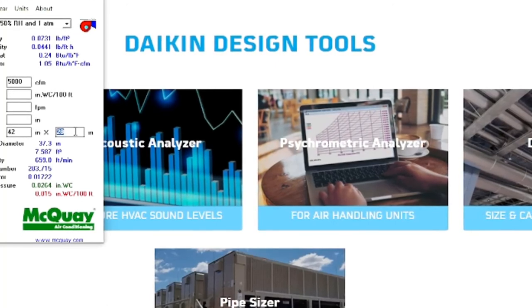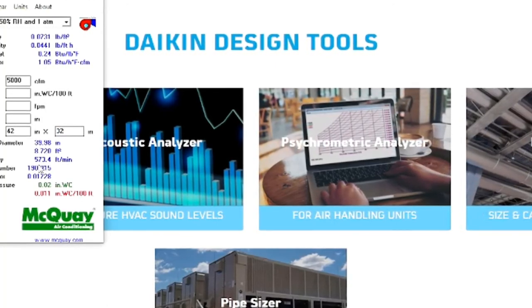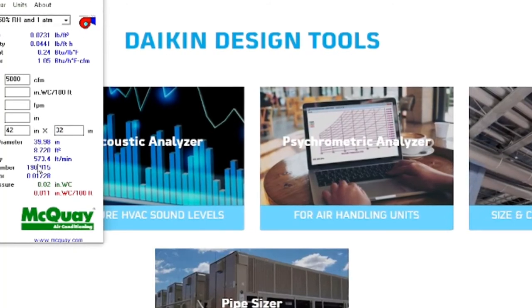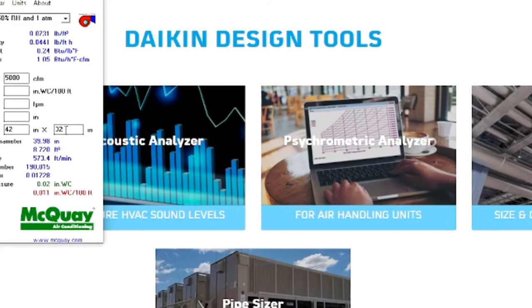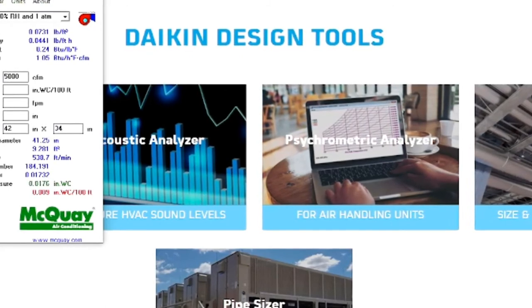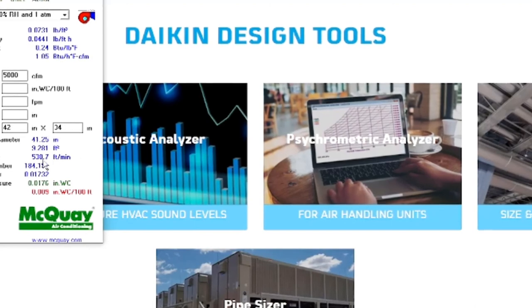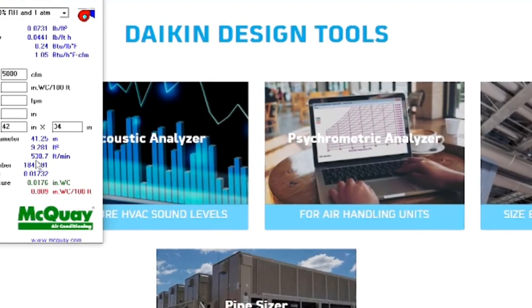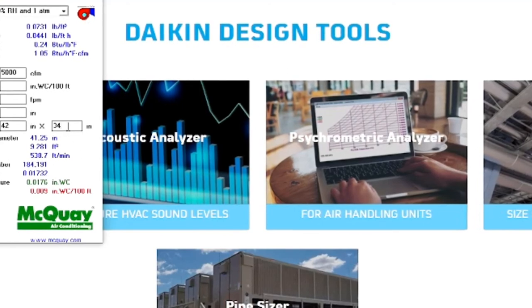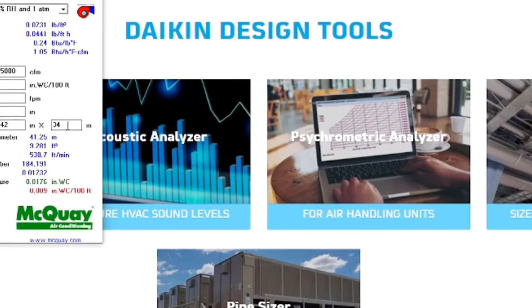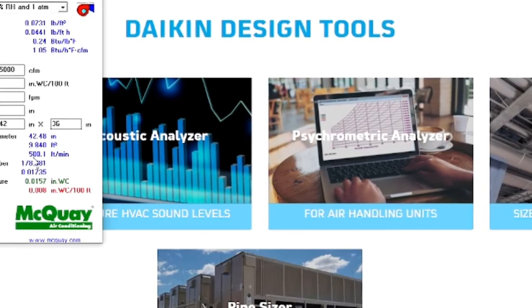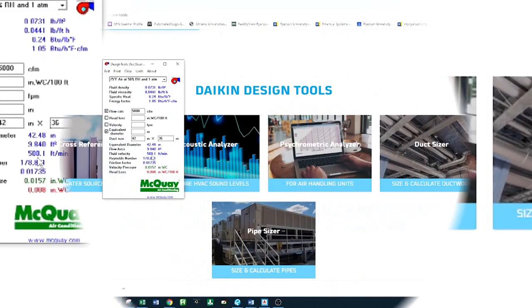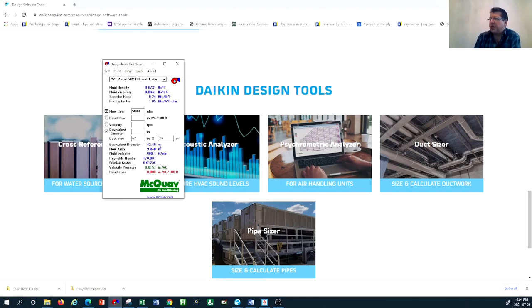I'm going to increase my duct size to 32 and then double check my velocity. So my velocity is now 573. So there is a little bit of trial and error we can apply. And at 34, I can see my velocity is decreasing as I increase the duct size. So I'm going to go to 36. And as you can see, I'm much closer to a fluid velocity of 500. I'm going to go to 38. And as you can see, as my velocity decreases, my head loss decreases as well in here.